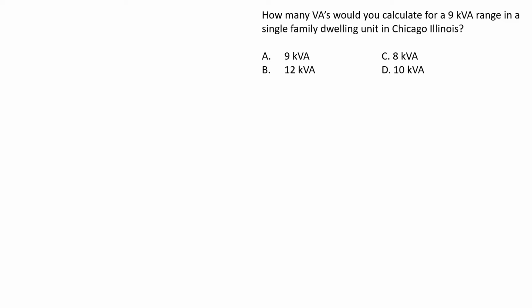In our case, our range falls into column C. It's asking for a 9 kVA range. So column C is a little different. It is not demand factors. It is a fixed kW rating. So any range that falls in between 8.75 and 12 is going to be 8 for 1, 11 for 2, 14 for 3, 17 for 4. That is the fixed load that you will have for your calculation.